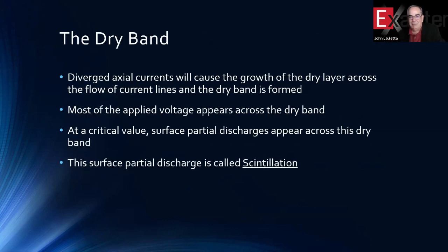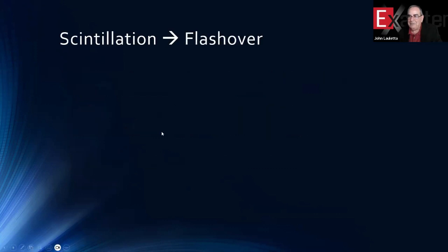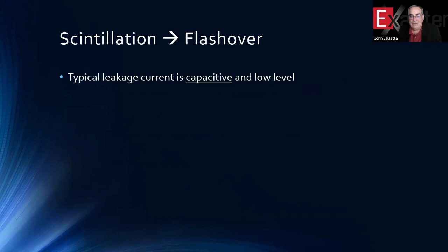So the dry band, we've talked a little bit about it. It's something you can't see typically. We looked at it in the laboratory in a number of ways, and the issue is you can find it with the emission of these very specific RF signatures. And by knowing how to listen for those, you can locate the source of that. And it's been studied in laboratories to the point where you can calculate statistically how many dry bands on an insulator will lead to that insulator flashing over. So there's kind of a threshold of the number of dry bands on the surface of an insulator. So scintillation will eventually lead to a flashover.